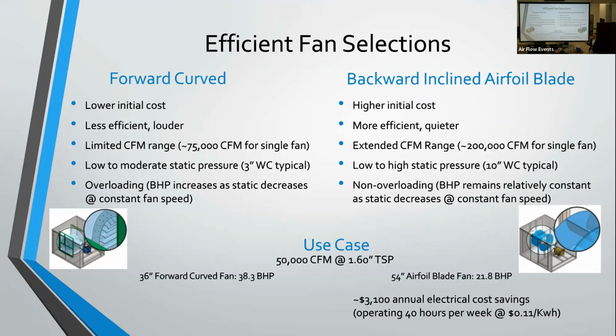You've got a half an inch of external static, and this at this point is the generous one. 1.6 is pretty low. A 36-inch forward curve fan is going to run at about 38.3 brake horsepower, which is not bad, I guess. If we were to put that at 2.6 inches, it would be substantially higher. It's just they're not great at higher static pressures.